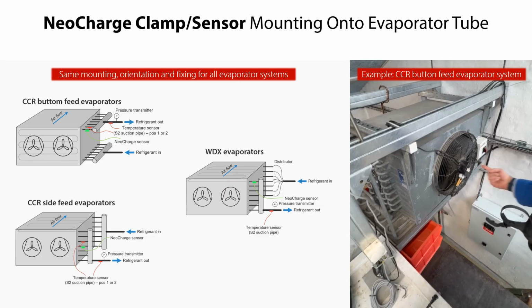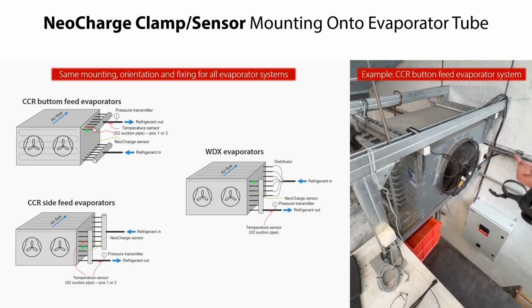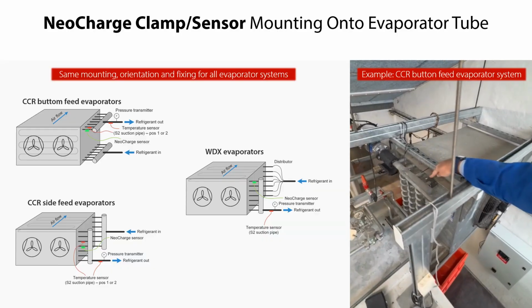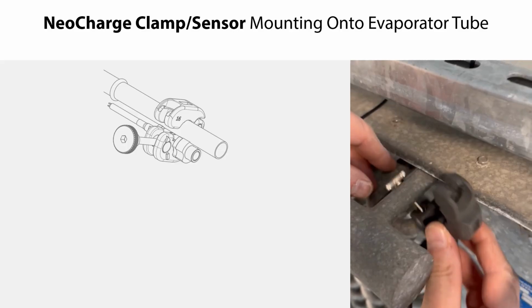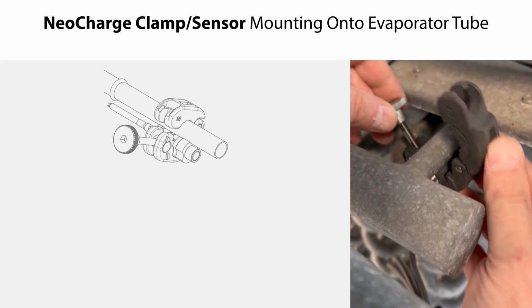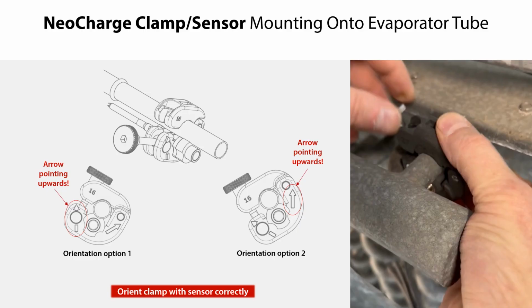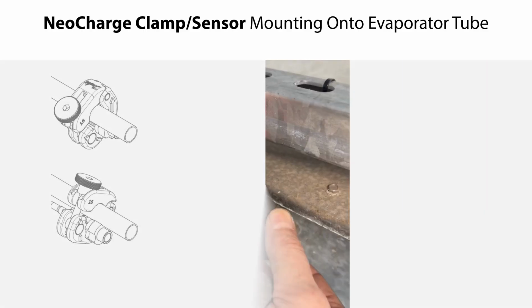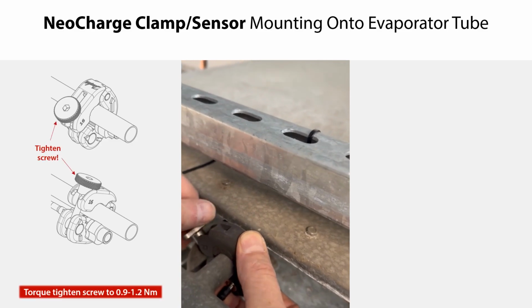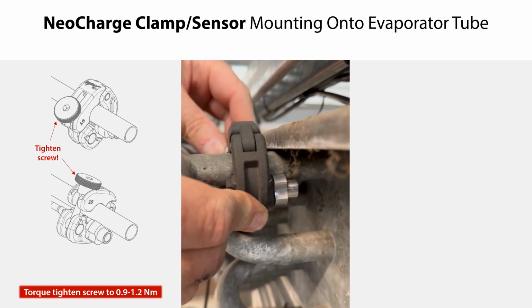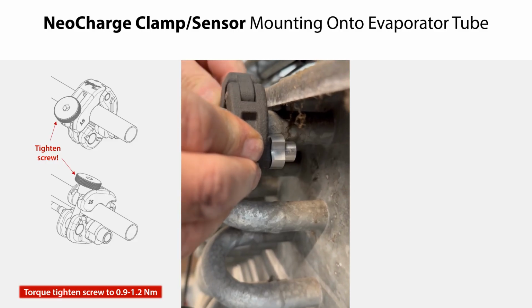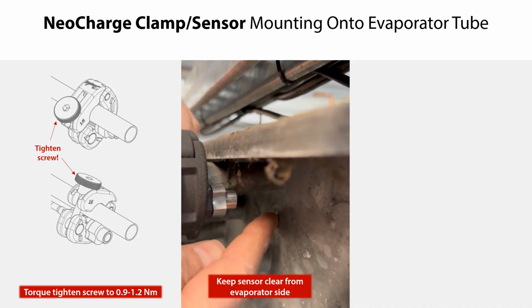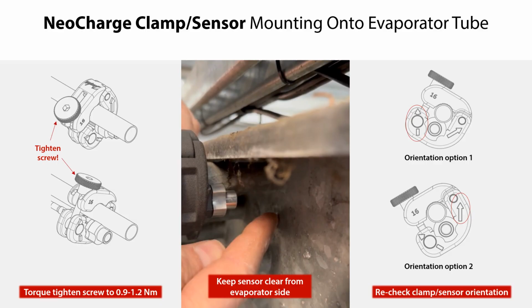In this example, we mount the clamp with sensor on a CCR bottom feed evaporator system, as indicated here. Therefore, open the sensor clamp and place it on the evaporator tube. Then close the clamp. Ensure that the clamp with sensor is oriented in one of the two positions specified here. Push the clamp screw into place in the clamp and tighten the screw as specified here so that the clamp with sensor is firmly fixed to the evaporator tube. Ensure that the sensor is clear from the evaporator side as indicated, and recheck that the clamp with sensor is correctly oriented on the tube, as mentioned earlier and specified here.